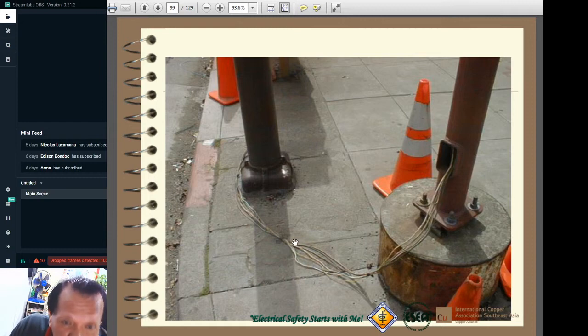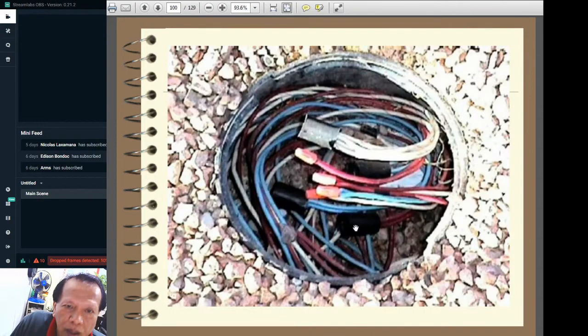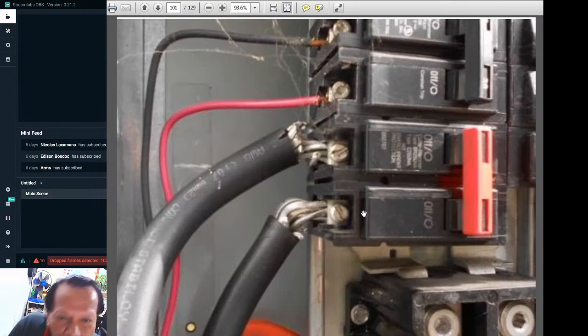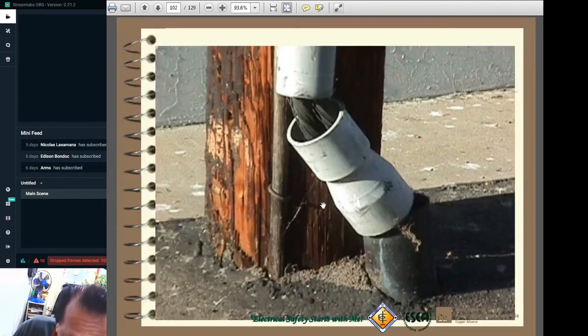So it's so dangerous that in the long run it might cause grounding and could cause electrocution. So this is done outside without proper construction of a safety manhole, an electrical manhole, which is also dangerous. And here, the technician who did the works just simply cut some of the strands of the wire, as you could see. Because the wire is quite big, he would cut some of the strands so that he would be able to fit a few strands on the terminal of the circuit breaker. So this is a violation of the code.